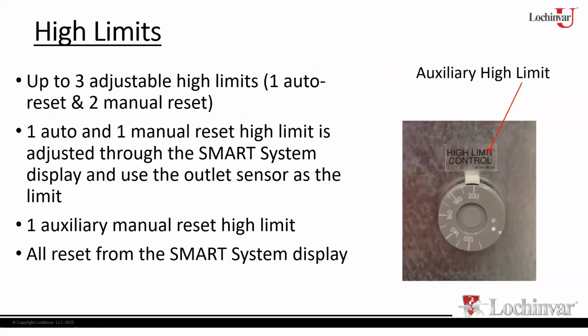All right, your high limits. You've got 3 high limits on this thing. There are 2 high limits that are built into the control module. They're part of the logic. So there's an auto and a manual reset high limit built into the control module. We'll talk more about that in a second. Then you've also got this auxiliary high limit, which is the gray dial high limit, which is also going to be sticking out the front of the jacket.